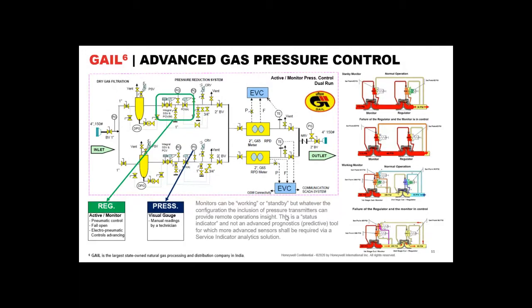And here we have what we call the monitor-active monitor setup, where a regulator in the green highlighted box, top left of center, the active regulator, is working as it says, active. It fails - it generally fails open, allowing more flow through or higher pressures. So then the monitor kicks in. It's just pneumatics.